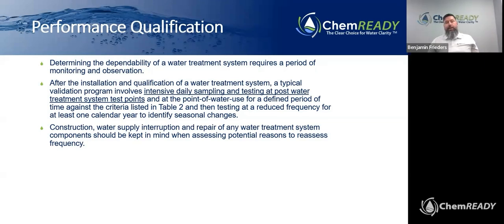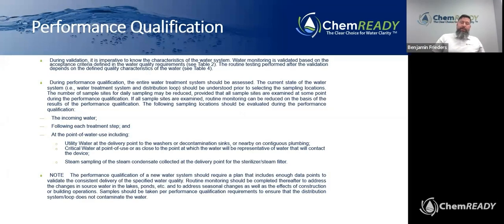Now, on the flip side, if you do 3 days in a row and they all come back different, right? The whole thought process behind this, and following each treatment step, is: okay, what piece of equipment is not performing consistently? Is it my RO? Do I need to switch out my DI? Once I get all the equipment that's supposed to be putting out water quality back to the less than, then you can reduce the frequency, but it's 100% based off of your individual results for your facility. Hopefully that wasn't clear as mud. Hopefully that answered the question.